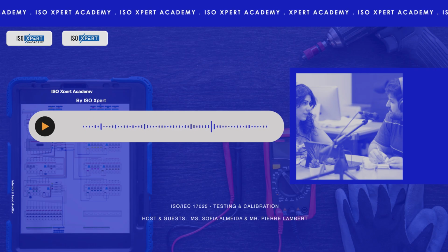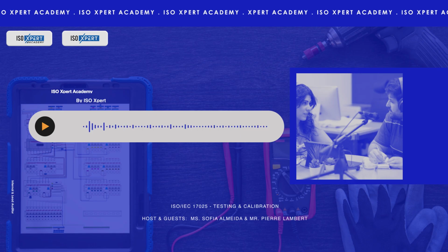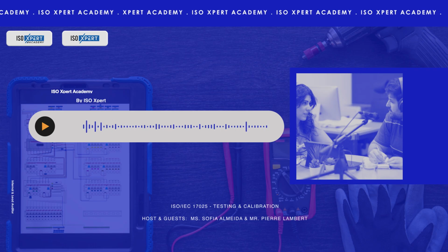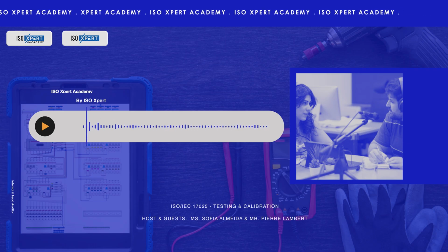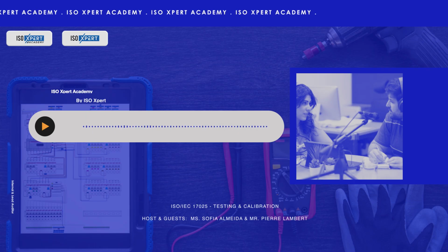This is kind of a cornerstone concept. It's about ensuring that every measurement the lab makes can be linked back through an unbroken chain of comparisons to fundamental standards, usually the SI units, the International System of Units, or sometimes to certified reference materials. So how do auditors check that chain? They literally trace the calibration chains. They'll pick a piece of equipment, look at its calibration certificate, see what standard it was calibrated against, then look at the certificate for that standard, and so on.